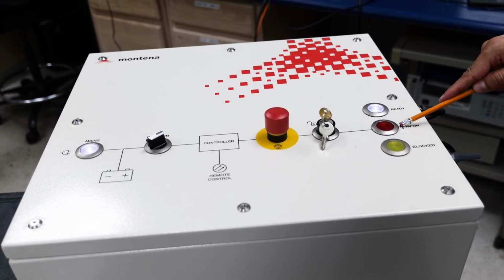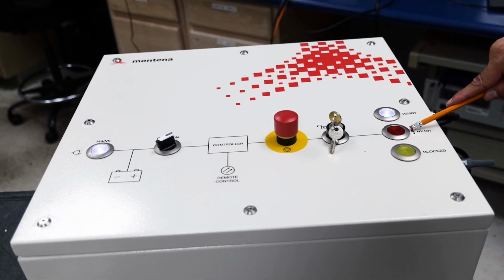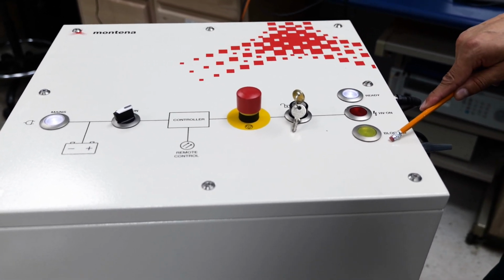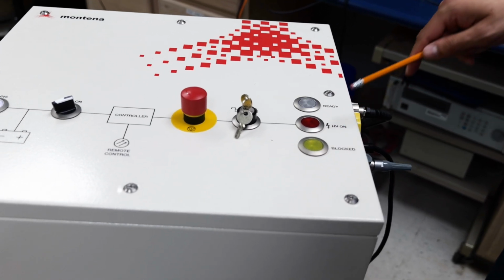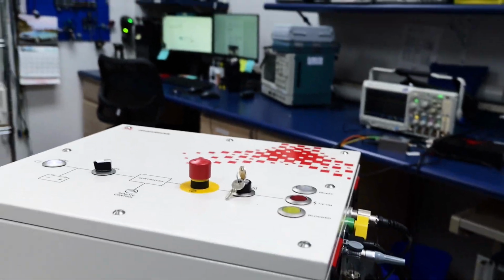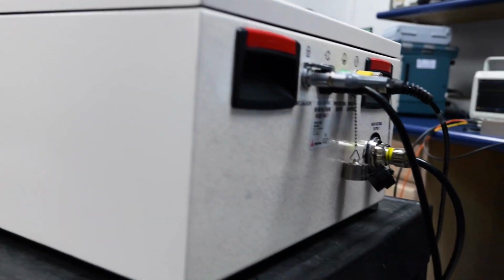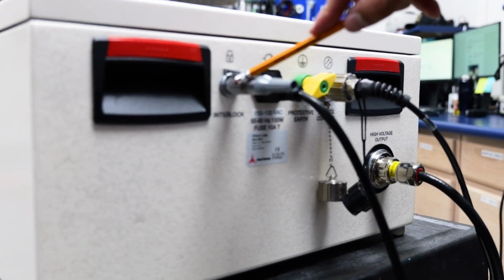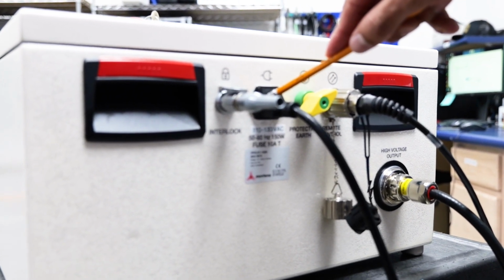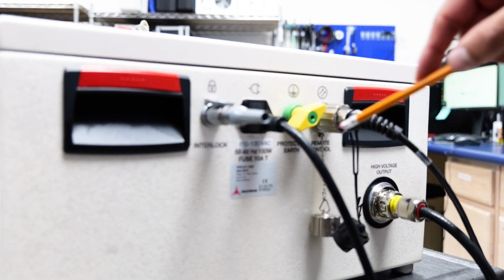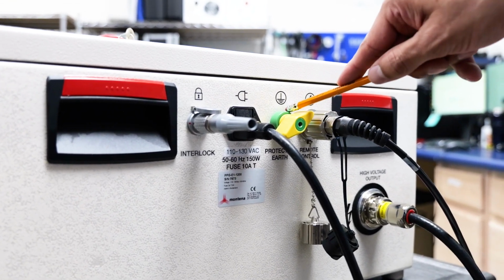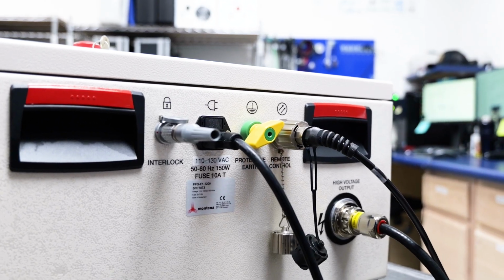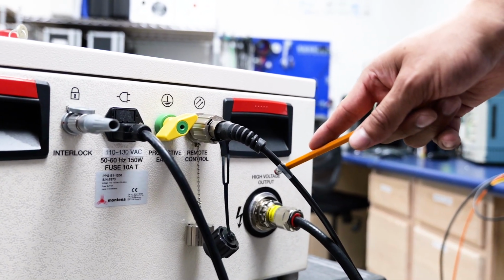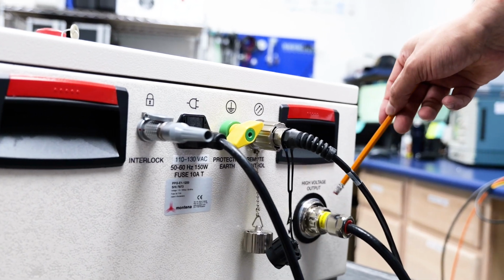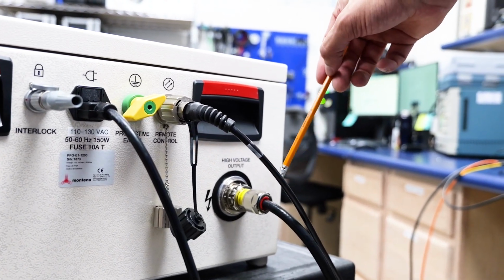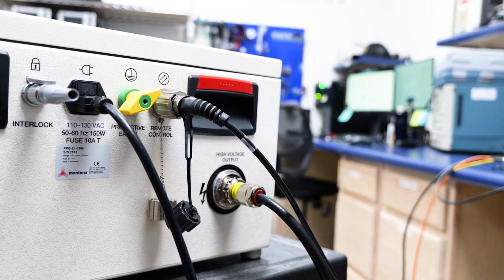Like I said, this is the ready light. When the high voltage is enabled, the red light will come on, and if the interlock is removed or the emergency stop is changed, the yellow light will come on. If we rotate here to the side of the pulse generator, we have the interlock connection switch here. We have the AC single phase input to power on and charge the battery. We have the ground connection. Here we have the communication link that goes to your PC and the communication hub. And here's the business end.